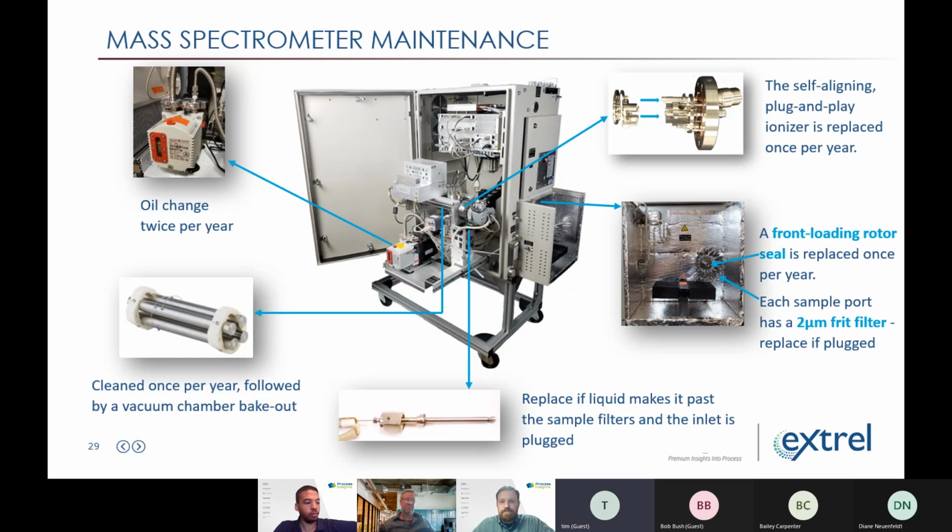We actually have one of these that's never been used because of a shift in economics. It's pretty old, like 8-10 years old. To do a flare, we would have to go to the Sulfinert and possibly the Hastelloy. This one was just for fuel gas analysis.